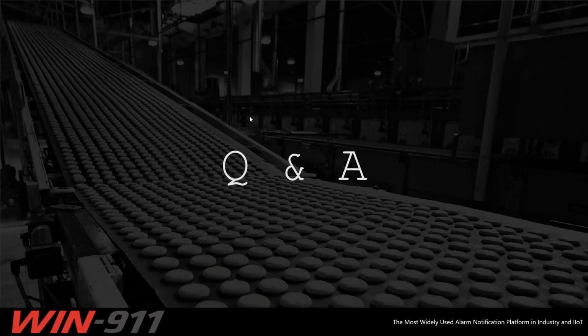Naeem asks: please clarify again, if WIN-911A has an issue, WIN-911B will be online and active, so we need to do a forced failover of SCADA 2. I'm not sure I completely understand, but to go over this again: if there's an issue on WIN-911A but your SCADA is still good, failing over to WIN-911B really wouldn't be a solution, because the secondary SCADA that WIN-911B is attached to should not be active, right? If it is, that's a different story, but typically we would be doing the failover based on the SCADA's activity.